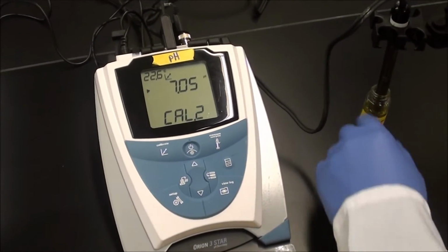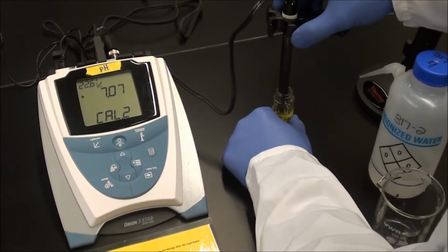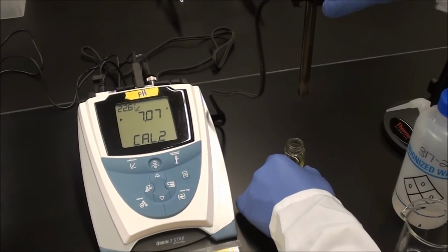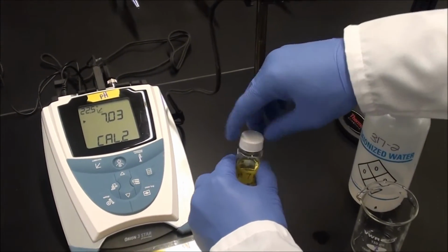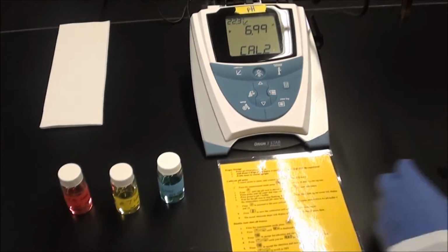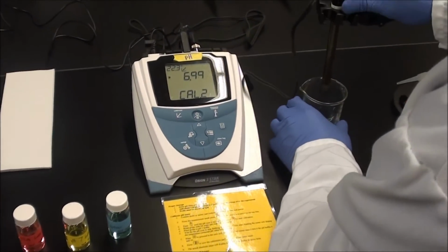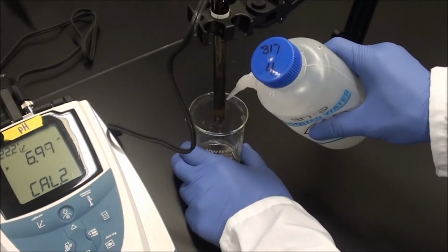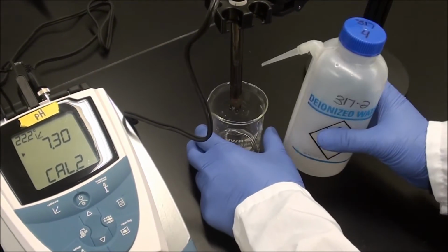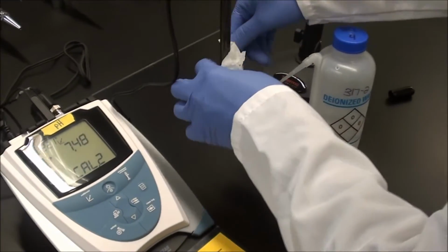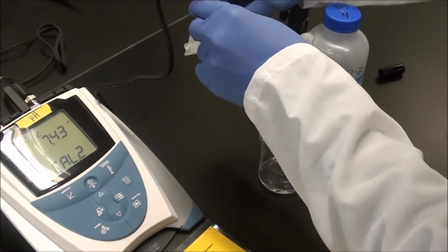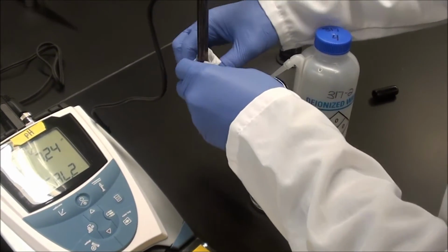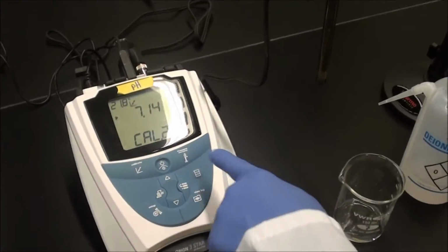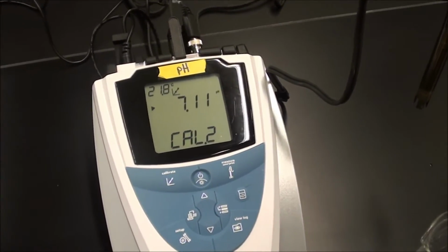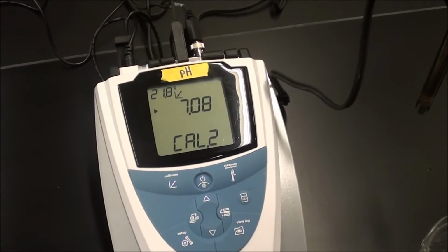For the next calibration point, we're going to take the pH probe out of the pH 7 buffer, make sure we cap the pH buffer and put it back in its place. We're going to go ahead and rinse the pH probe with DI water and wipe it with Kim wipes. And now on the screen it should say calibration 2, for which we're going to be using pH buffer 4.